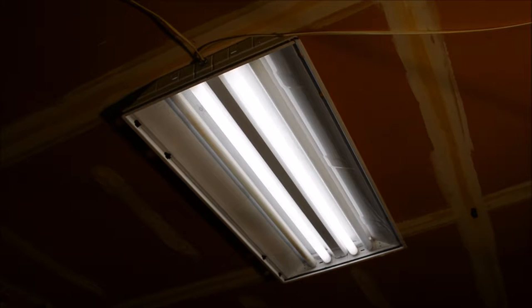Now as you'll see, two of the lights are still on on this light. The outer pair are not. That's because the ballast usually runs two lights at a time. So in this light fixture, there are two ballasts. We're going to be replacing the faulty one.